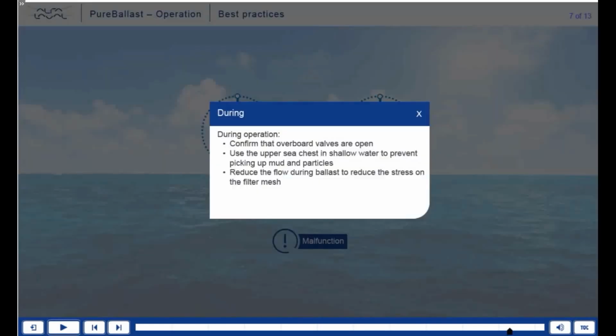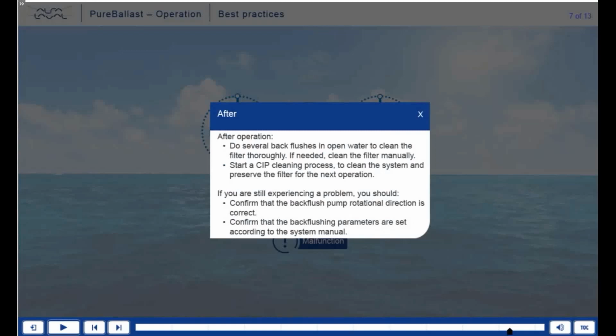During operation, confirm that overboard valves are open. Use the upper sea chest in shallow water to prevent picking up mud and particles. Reduce the flow during ballast to reduce the stress on the filter mesh. After operation, do several backflushes in open water to clean the filter thoroughly. If needed, clean the filter manually. Start a CIP cleaning process to clean the system and preserve the filter for the next operation.